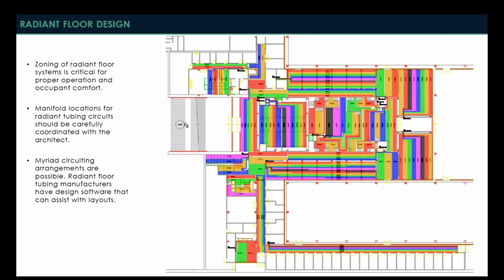Another important aspect of radiant floor design is the aspect of zoning. So all of these systems need to be zoned out appropriately so that you're addressing both the interior loads and exterior loads, you're keeping the circuits close to where the radiant manifolds are located, and that you're maintaining comfort conditions throughout a space. In very large areas, you're going to have 4, 6, 8, 12 different circuits serving that zone. So each of these circuits needs to be laid out in such a way that you're able to maintain a consistent thermal environment.